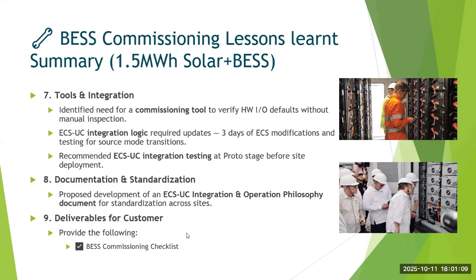Documentation should also be clear on how the overall EMS to unit controller, which operates the overall BESS, works, and what the philosophies are: either we are going with frequency regulation or load peak shaving, what applications we have, what modes we have, and in each mode how the BMS and PCS work. We need to have all those things. Then with all that experience and the delays in commissioning, we came up with a commissioning checklist that can be a reference for all projects down the line.